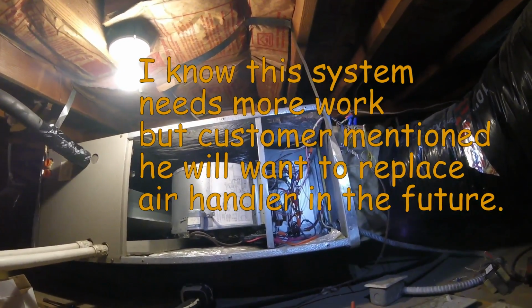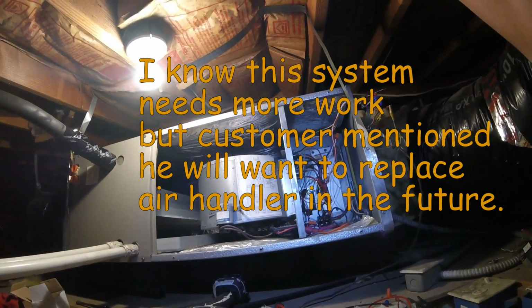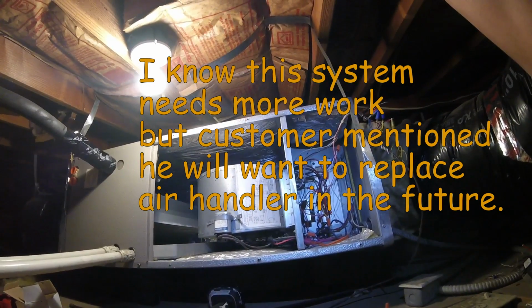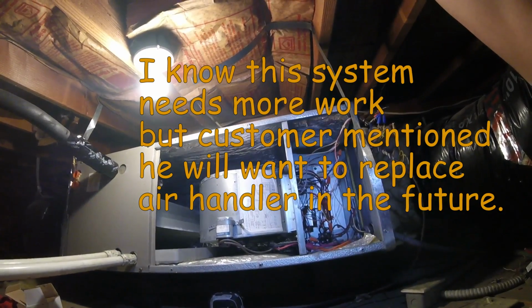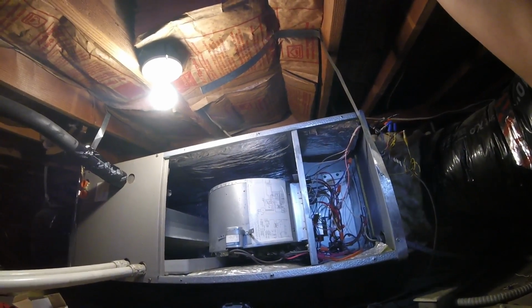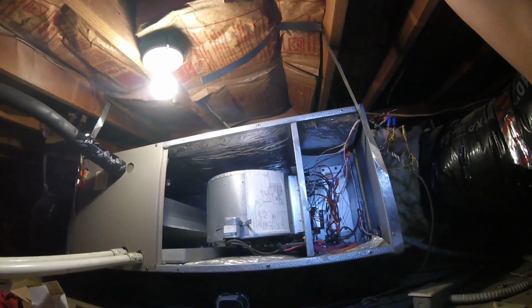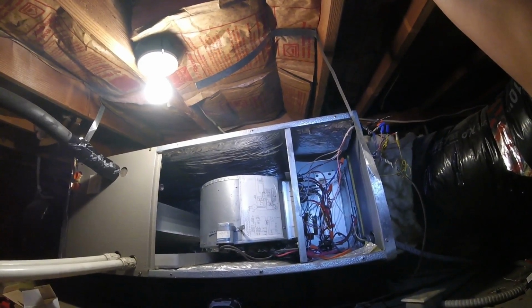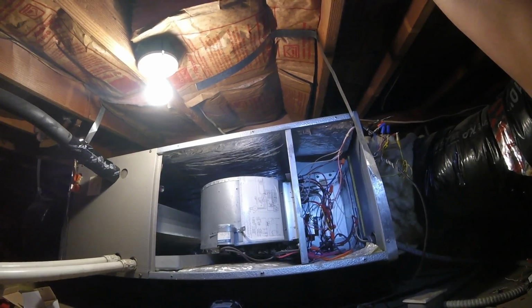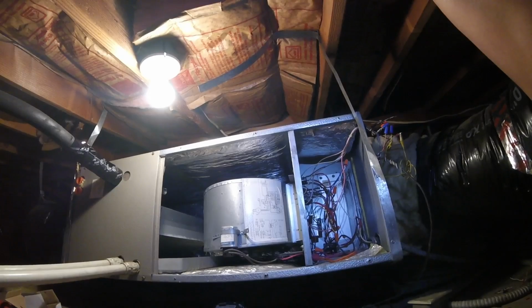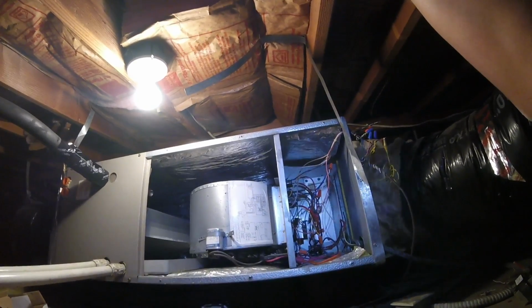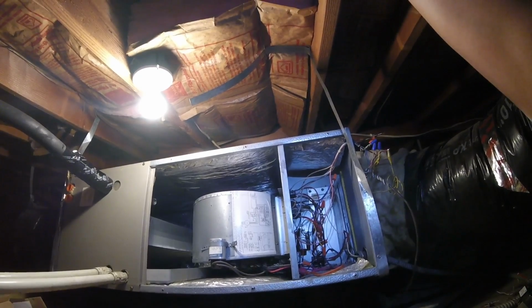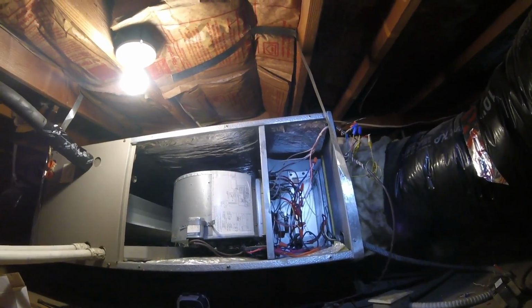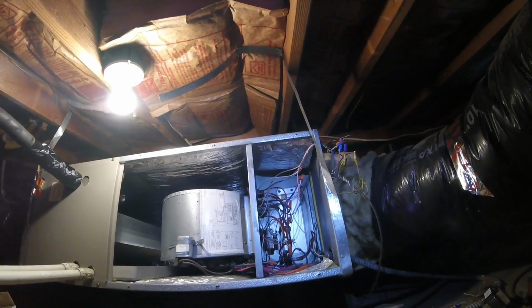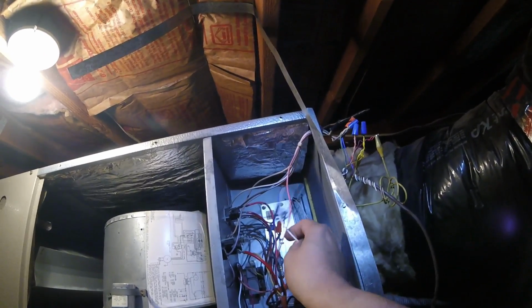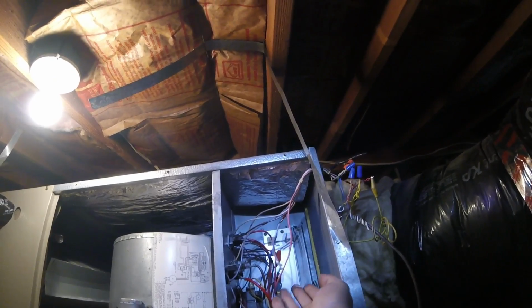Original call, it was acting weird, turning on, turning off at odd times. I found that the thermostat was not programmed for heat pump. Customer installed it. Had to change the dip switches in the thermostat. Then wired the thermostat back on, turned it on heat mode, it worked. Tested it on cooling and the transformer exploded. That's when I came up here and checked the wiring, and I found that in the air handler there was no ground to the transformer, so I put this ground.